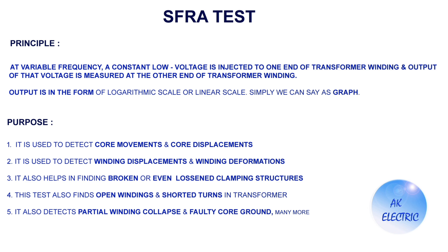Now let's see the purpose of this test. It is used to detect core movements and core displacements. It is used to detect winding displacements and winding deformations. It also helps in finding broken or loosened clamping structures. This test also finds open windings and shorted turns in transformer. It also detects partial winding collapse, faulty core ground, and many more.